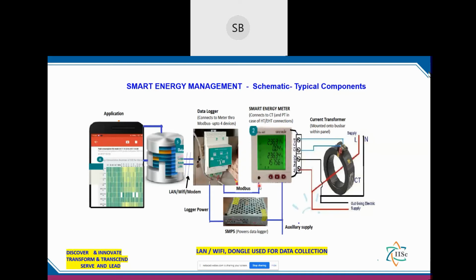One terminal of the smart meter is connected to a data logger through Modbus. This data logger connects to the meter through Modbus and can take a maximum of 4 smart meter devices, so 4 smart meters can be connected to a single data logger, because the data logger is costly. So we try to optimize and see whether we can bring down the number of smart meters. I mentioned 260 meters, but the data loggers may not be 260, so depending on the departments, we have tried to look into that aspect too.